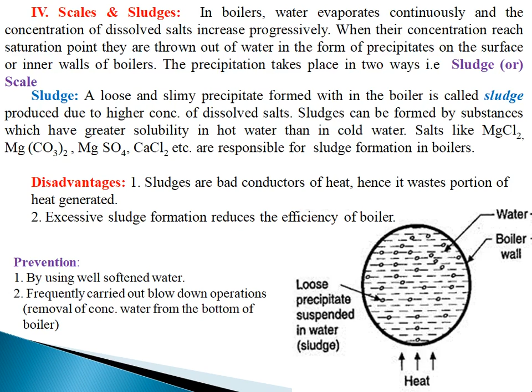Sludge formation can be minimized or prevented by frequent blowdown operation. Blowdown operation means removal of suspended impurities. And also by using well softened water, we can minimize the sludge formation. Next, scale. Before that, we have to know the scale definition. Scale is a hard adhering coating on the inner walls of the boiler. The salts like calcium sulfates and calcium bicarbonates are responsible for scale formation in boilers.